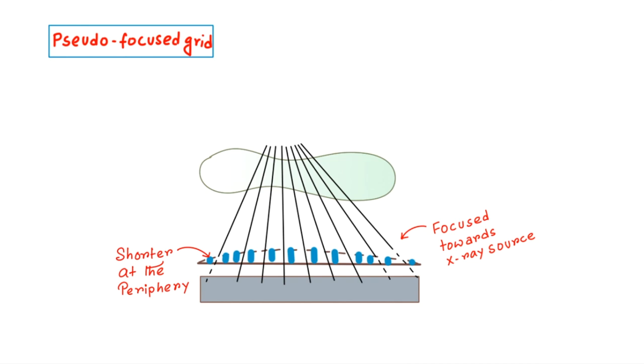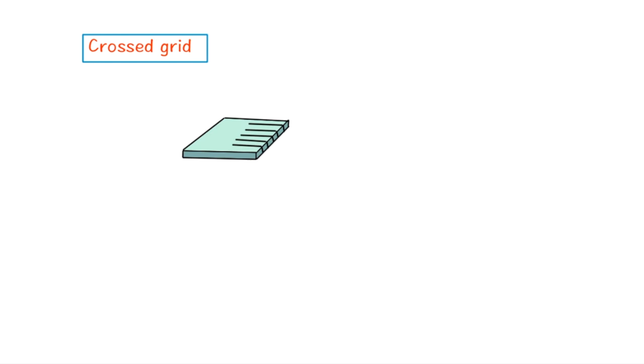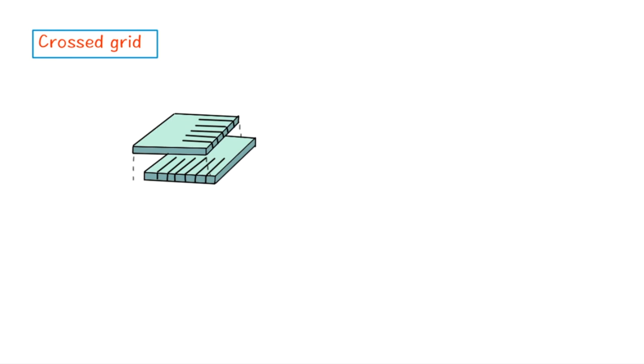Now the last type of stationary grid is cross grid. In this type, two grids are placed at right angle to each other. This type of grid is used to eliminate the X-ray photons which are scattered in the plane of lead strips.